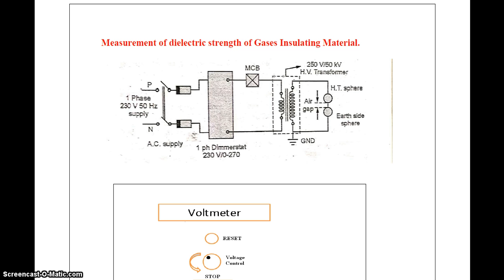Then the properties of gaseous insulating material: fine heat transfer, incombustible, chemical inertness against the construction materials used, environmentally non-poisonous, small temperature of condensation, high thermal constancy, available at low cost. Then the applications of dielectric gases: used in transformers, radar waveguides, circuit breakers, switchgear, high voltage switching. They are usually used in high voltage applications.